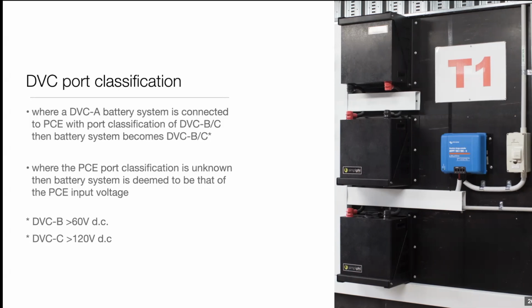But because the PV array is operating at DVC-B levels and there's no galvanic isolation between the PV array and the battery, we now deem the battery port to be DVC-B as well, which means that we have to have double insulated cables. We have to have adequate mechanical protection as per AS/NZS 3000, and also that's licensed electrical work on that battery, even though it's a 48 volt battery, because of the DVC classification. So this is really something that is new to the industry, that with non-galvanically isolated maximum power point trackers you need to consider the port classifications very carefully.